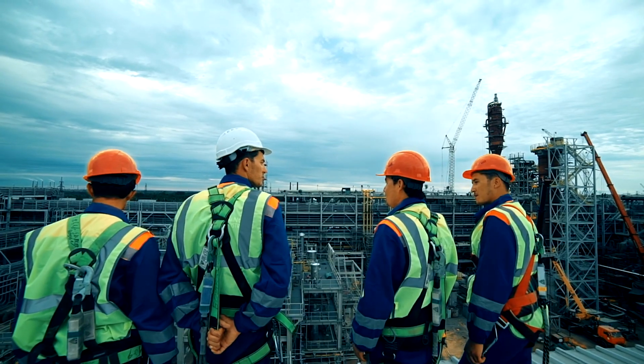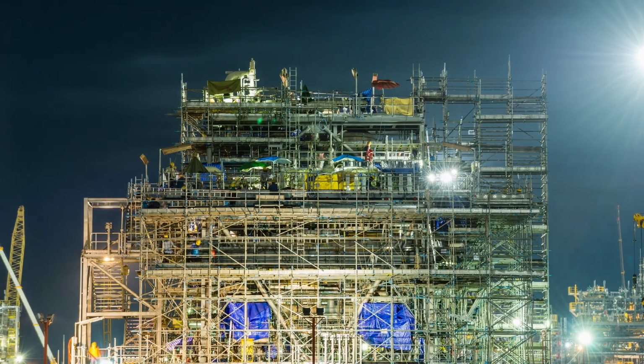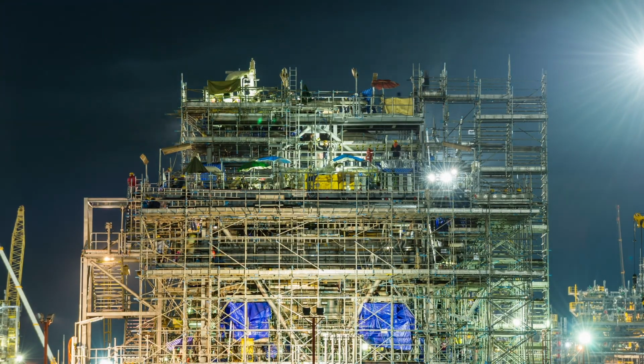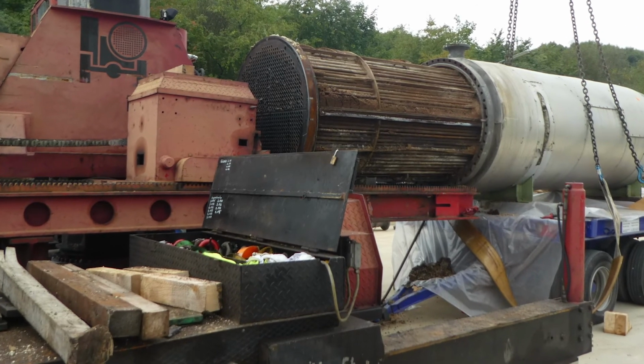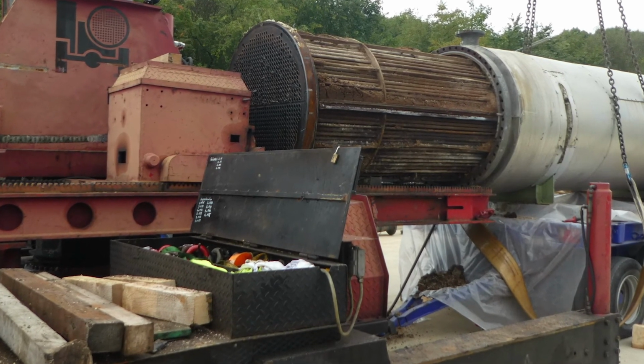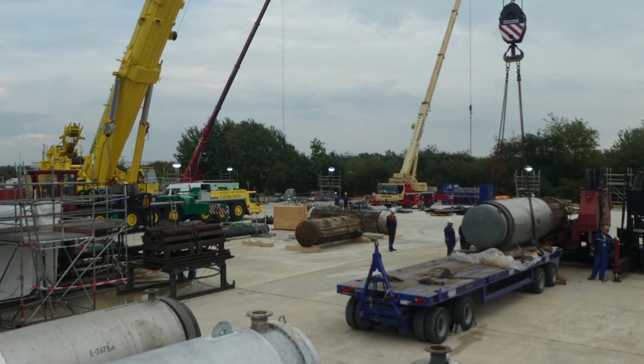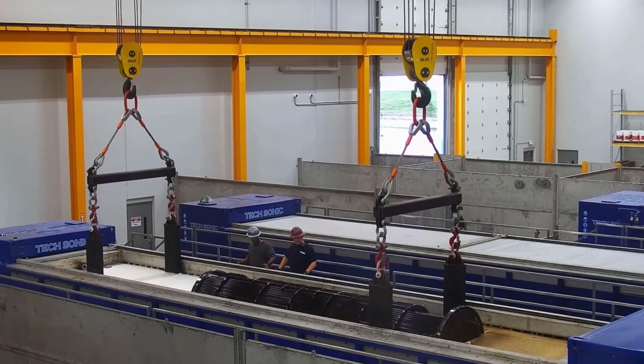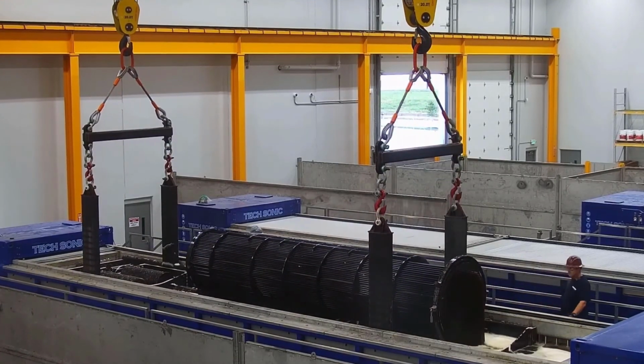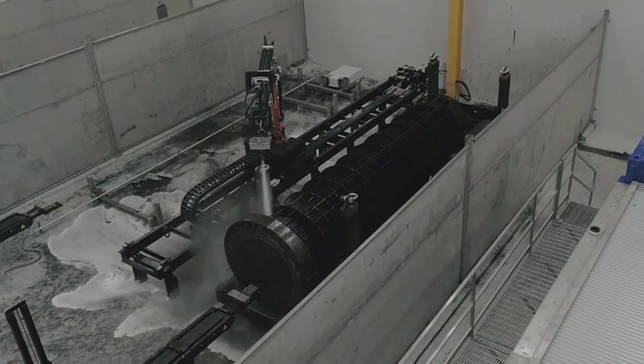Clean as New can actually help in a couple of different scenarios in terms of the exchangers being cleaned. The second approach is also in a turnaround, which is normally a 30 to 45 day event, with millions of dollars of lost opportunity while the unit is down having maintenance performed on it. Clean as New can come in, pull those exchangers, get them clean, provide a 20 to 25% efficiency savings, and halve the schedule impact to their plan, allowing them to manage that time frame down.